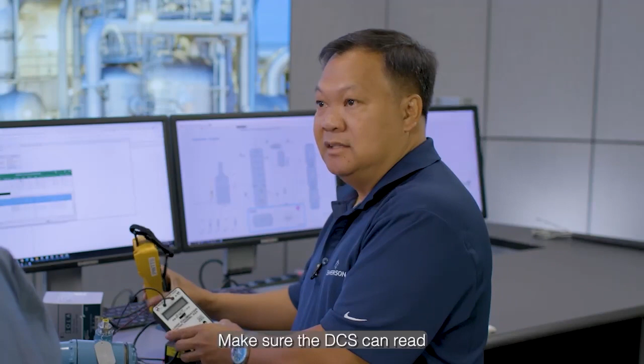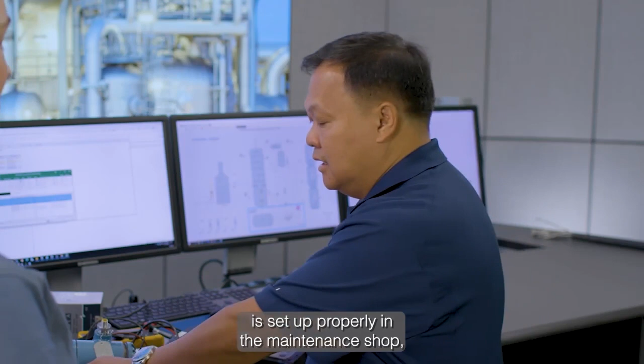Tin, that's a lot of steps. How long can it take to commission one device? Just to make sure the device is set up properly in the maintenance shop normally takes about an hour or so. But the most time-consuming piece is getting all the people - depending how high the scaffold is you need two people, getting the work permit done, and making sure every instrument is calibrated properly. It could take a couple of days.